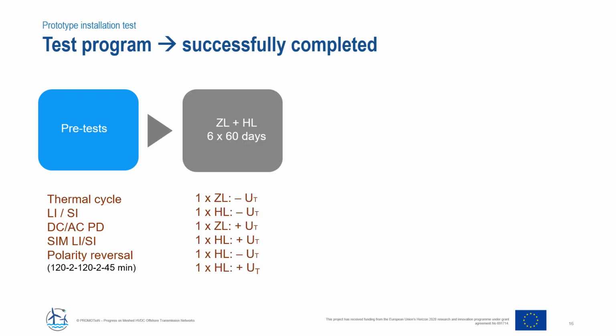After the pre-test, which is basically a check procedure that the HVDC GIS is ready for the long-term test, it is then put under, of course, the actual test. And the actual test has 6 blocks, each block lasting for 60 days.